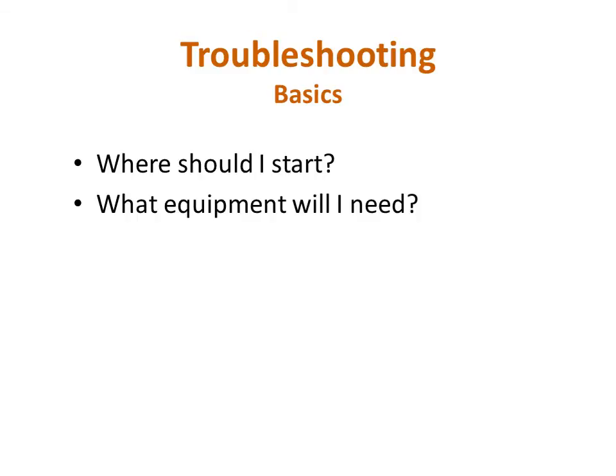The most useful equipment to have available, aside from knowledge of the error codes and a wiring schematic for the logic box, is a good multimeter. You will need to be able to measure voltages, not with a test light, since actual values are more useful, as well as to check continuity and possibly measure resistance. The other tool that is helpful to have is a short jumper wire that can be used to simulate switch presses in the logic box by bridging the appropriate switch input contacts.